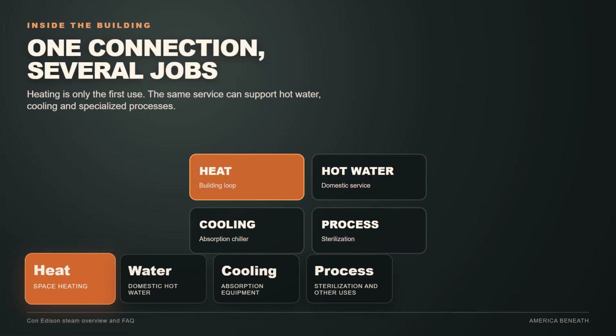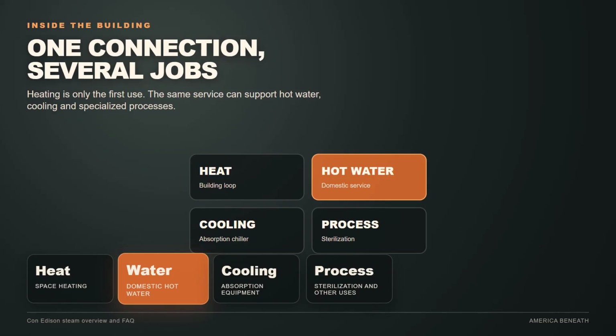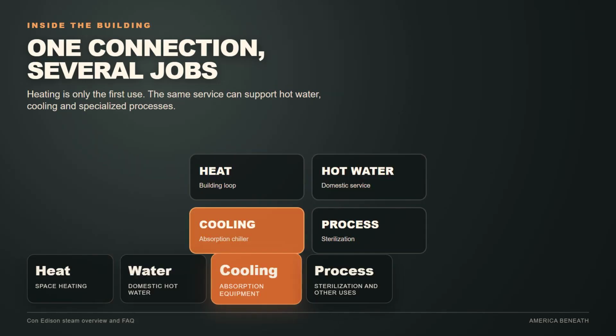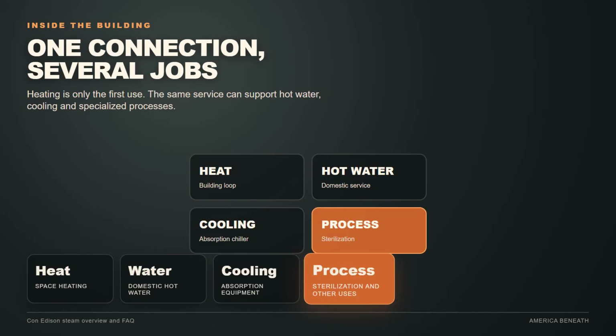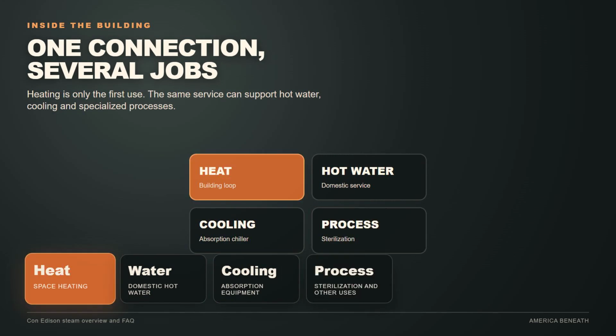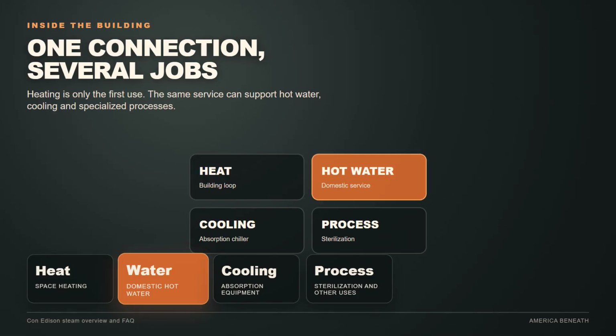The first job is the obvious one. Steam carries thermal energy that a building can use for space heating. But the same incoming service can support more than warm rooms. It can help produce domestic hot water. It can support humidification, cleaning, or other building processes. In some hospitals, steam can serve sterilization equipment, where dependable high-temperature service matters directly to operations. In commercial buildings, it can also supply absorption chillers. Those machines use heat as an input to help produce chilled water for air conditioning. Not every customer uses every one of these functions. That would depend on the building and its equipment.